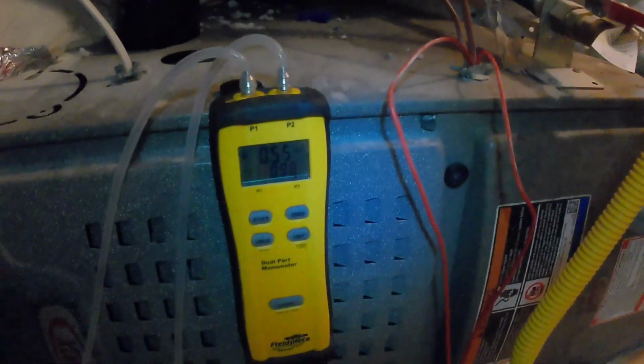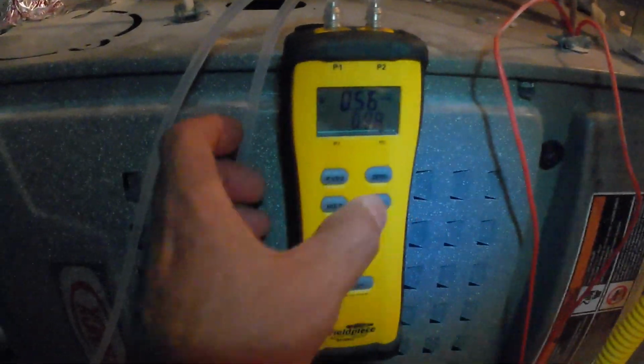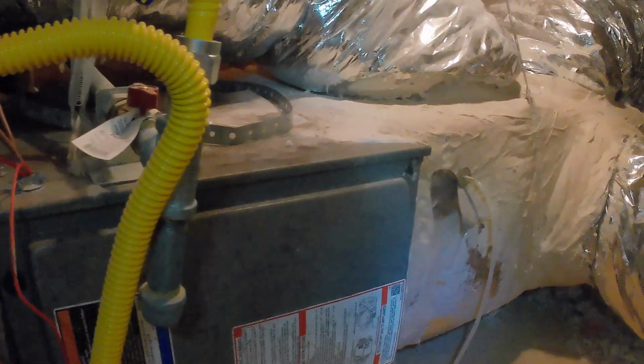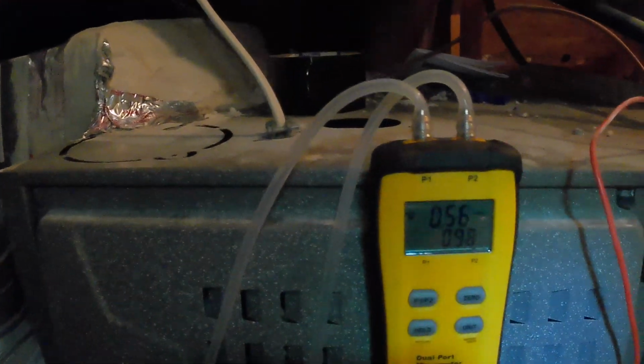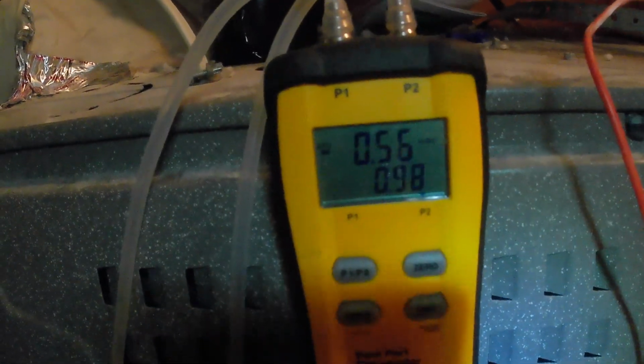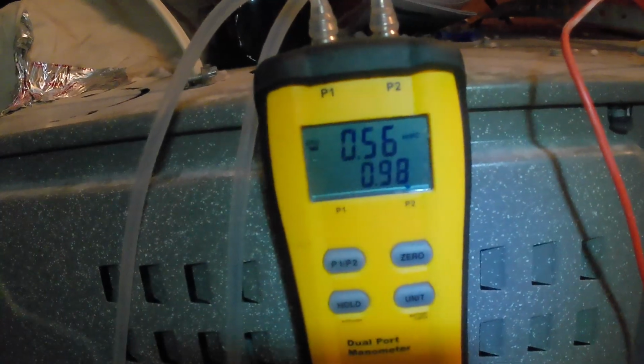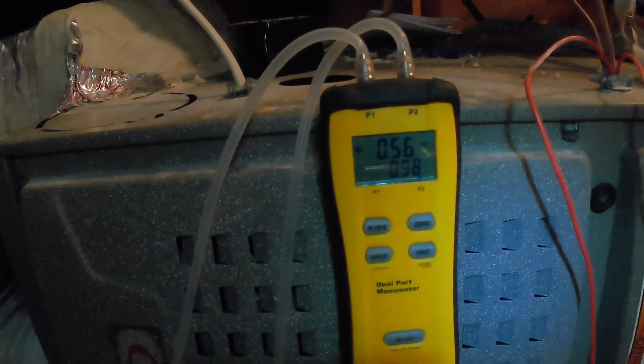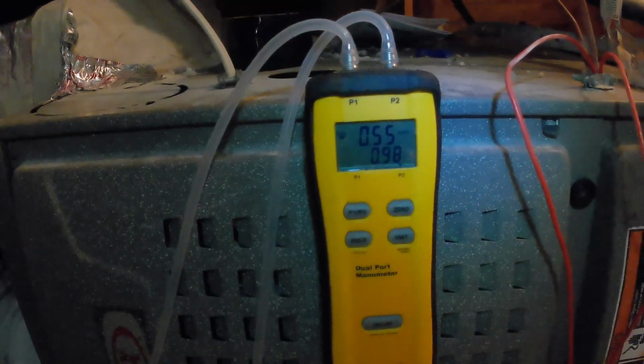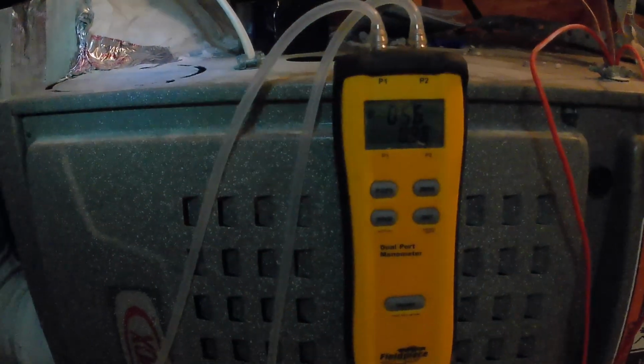Okay, so we're checking static pressure right now. 0.56 water column. We have one probe on the return and the other one in the supply. So 0.5 - unfortunately I don't have my ductulator right now, but I'll confirm that later on, and I'm pretty sure we are pushing the 1200 CFMs that these units require.